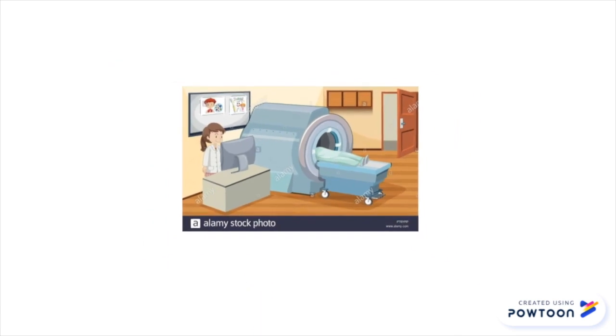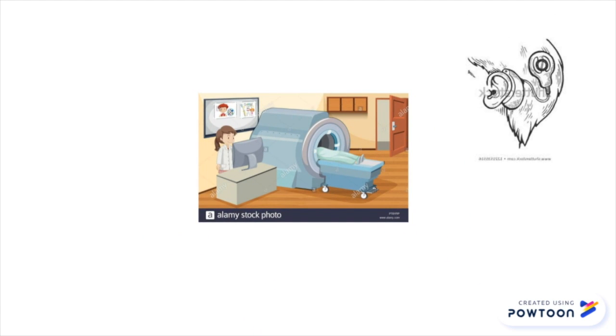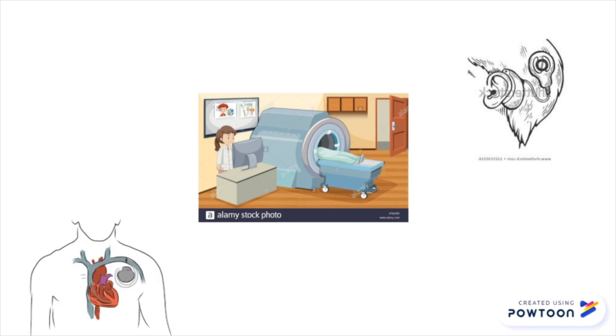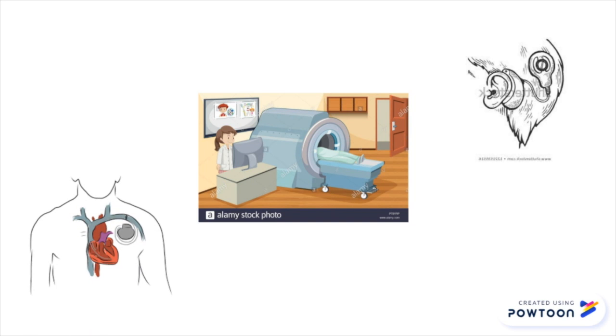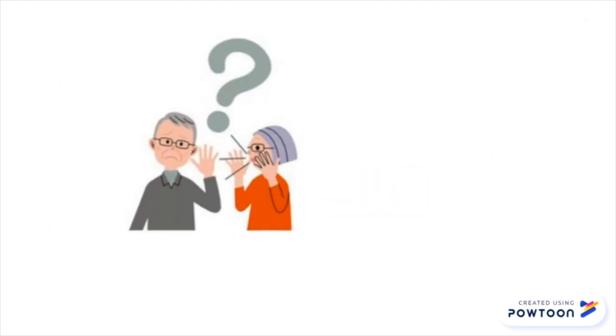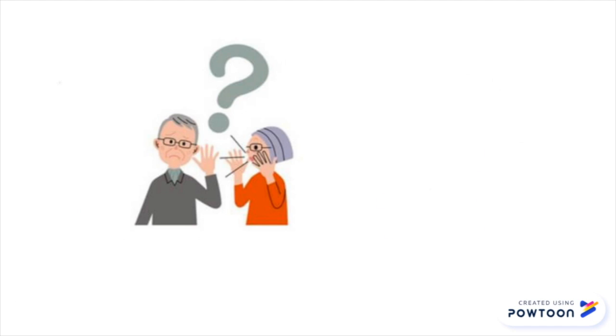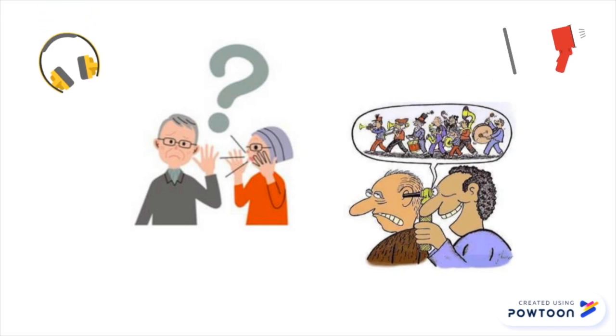Unfortunately, there are safety concerns associated with MRI scanners, and it's typically an issue with patients with internal implants, such as artificial joints, cochlear implants, stents, and pacemakers. The strong magnetic field of an MRI scanner can pull and potentially dislodge the implant, and strong radio frequencies can heat up the implant, in severe cases causing damage and burning surrounding tissue. Patients may also experience temporary hearing loss, and in severe cases, tinnitus due to large knocking noises made by the pulsed gradient field of the MRI.